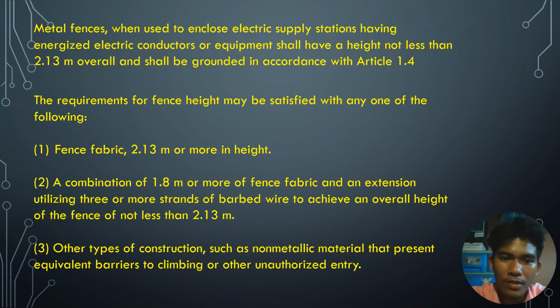The requirements for fence height may be satisfied with any one of the following: fence fabric 2.13 meters or more in height, a combination of 1.8 meters or more of fence fabric and an extension utilizing 3 or more strands of barbed wire to achieve an overall height of the fence of not less than 2.13 meters. Other type of construction such as non-metallic material that presents equivalent barrier to climbing or other unauthorized entry.